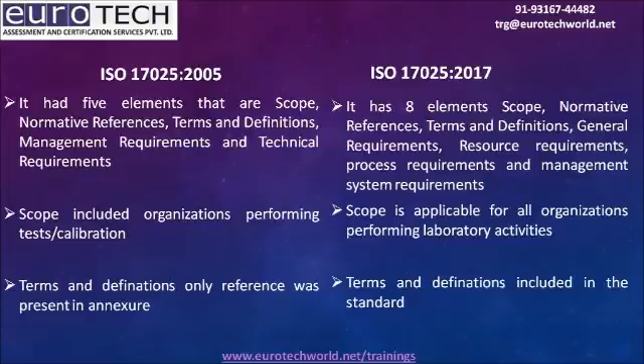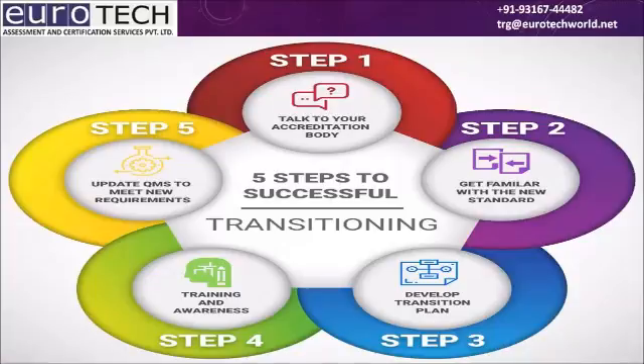ISO 17025-2005 had five elements: scope, normative references, terms and definitions, management requirements, and technical requirements. ISO 17025-2017 has eight elements: scope, normative references, terms and definitions, general requirements, resource requirements, process requirements, and management system requirements. In 2005 the scope covered organizations performing tests and calibration, while in 2017 it is applicable to all organizations performing laboratory activities. In 2005, terms and definitions only referenced an external document, while in 2017 terms and definitions are included within the standard itself.